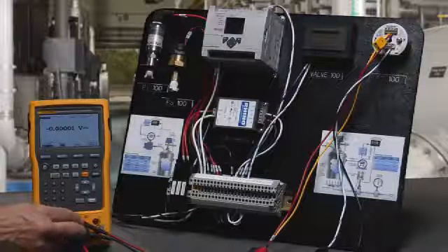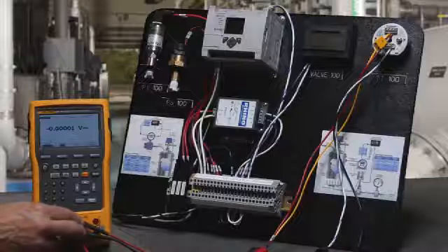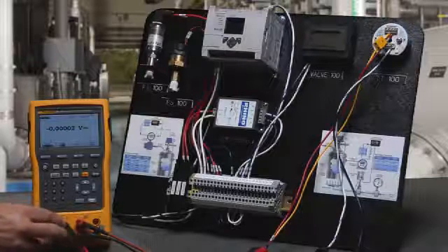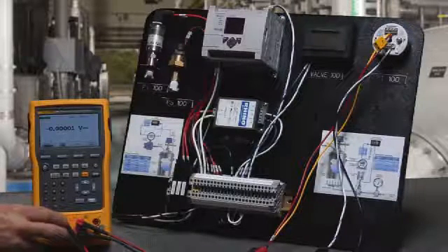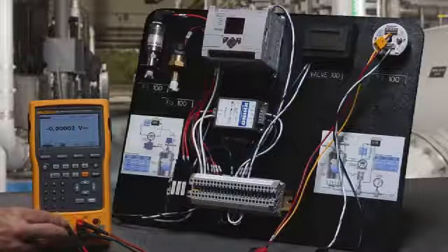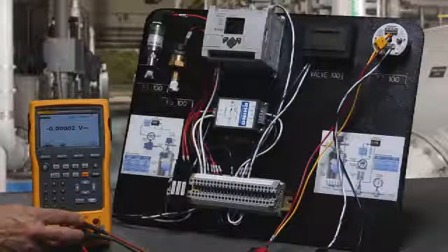We're going to power the transmitter and measure the milliamp signal measured back on the milliamp input jacks of the calibrator, and we're going to simulate an RTD input into the transmitter while simultaneously measuring the milliamp output signal.